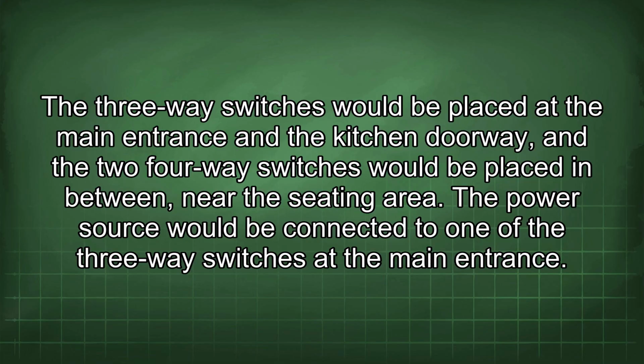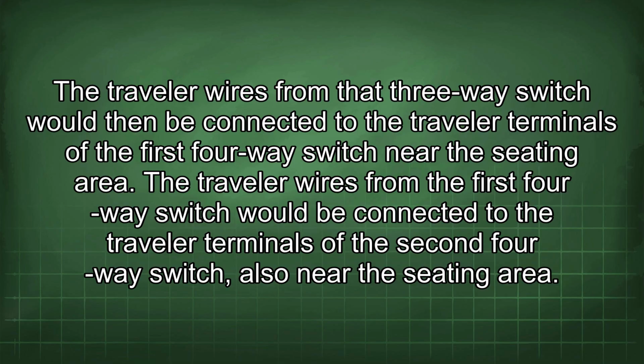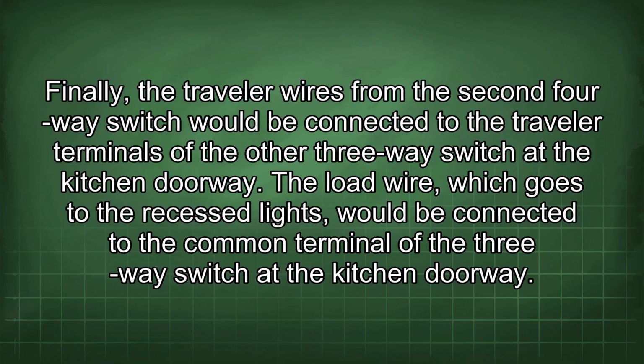The power source would be connected to one of the 3-way switches at the main entrance. The traveler wires from the 3-way switch would then be connected to the traveler terminals of the first 4-way switch near the seating area. The traveler wires from the first 4-way switch would be connected to the traveler terminals of the second 4-way switch, also near the seating area. Finally, the traveler wires from the second 4-way switch would be connected to the traveler terminals of the other 3-way switch at the kitchen doorway.